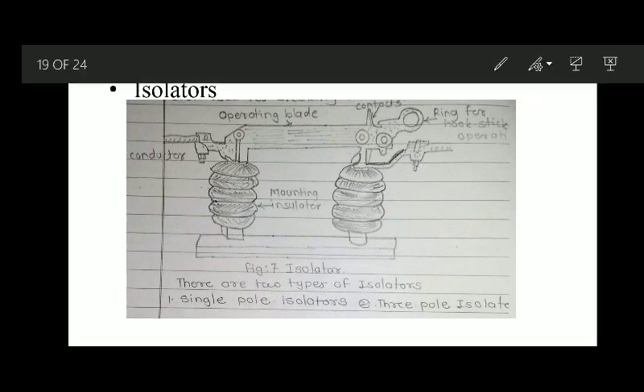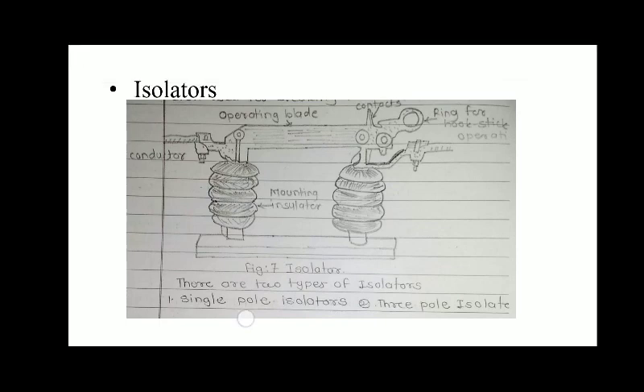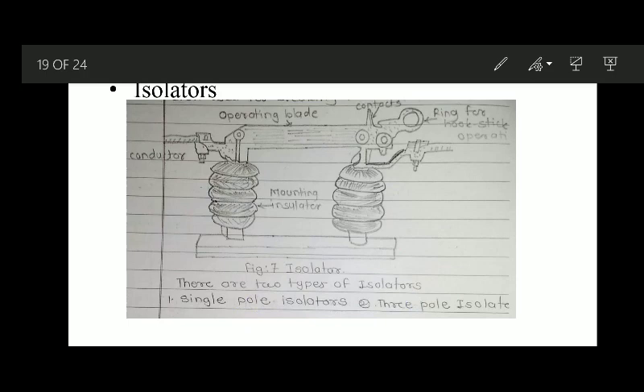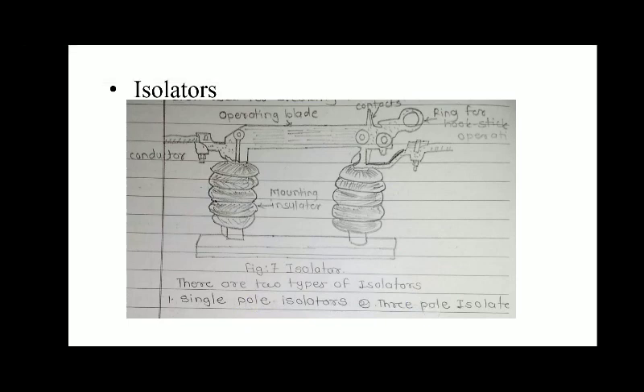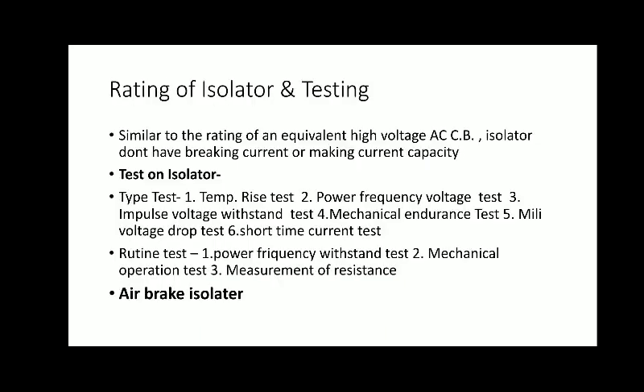There are actually two types of isolator: first, single pole isolator, and second, three pole isolator. A single pole isolator is used for single phase, and a three pole isolator is used for three phase. You can also use single pole isolators for three phase, but three different units, that is three single pole isolators, are required for a three phase system. So this is the diagram of an isolator. After that we want to see the rating of isolator and testing.